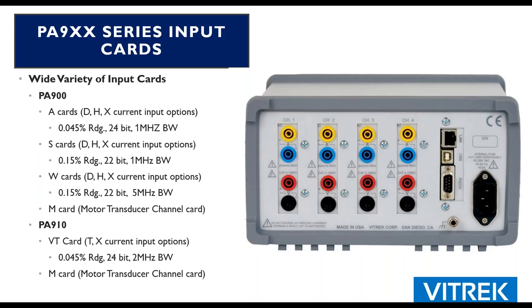So for our PA900 series power analyzer, there are 4 different types of cards that can be inputted into the back of our unit. If you take a nice close look at the picture of the back panel, you'll notice right under where it says channel 1, you see a little AD on there. That happens to be the AD card. Now our A card is our most accurate card, providing 0.045% of reading with 24-bit resolution and a 1 megahertz bandwidth.